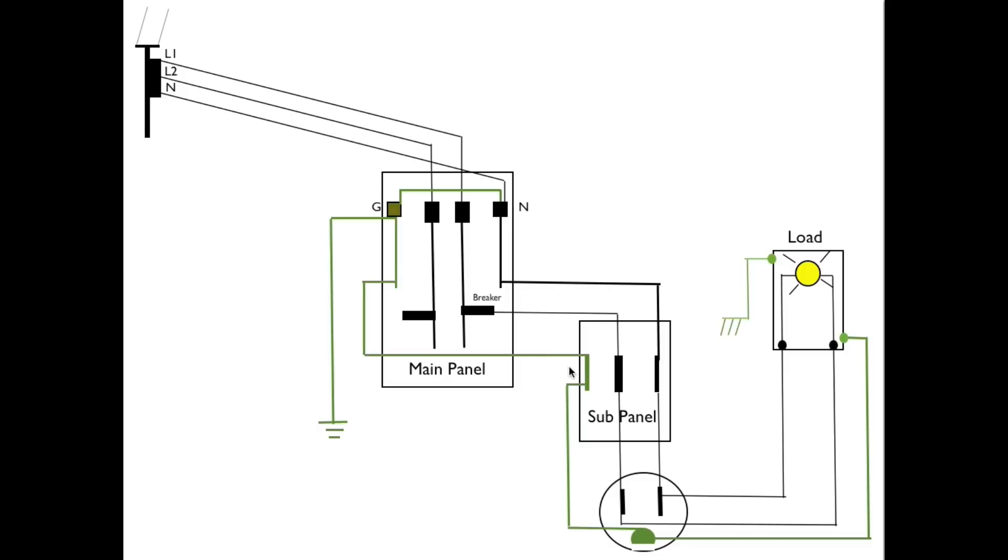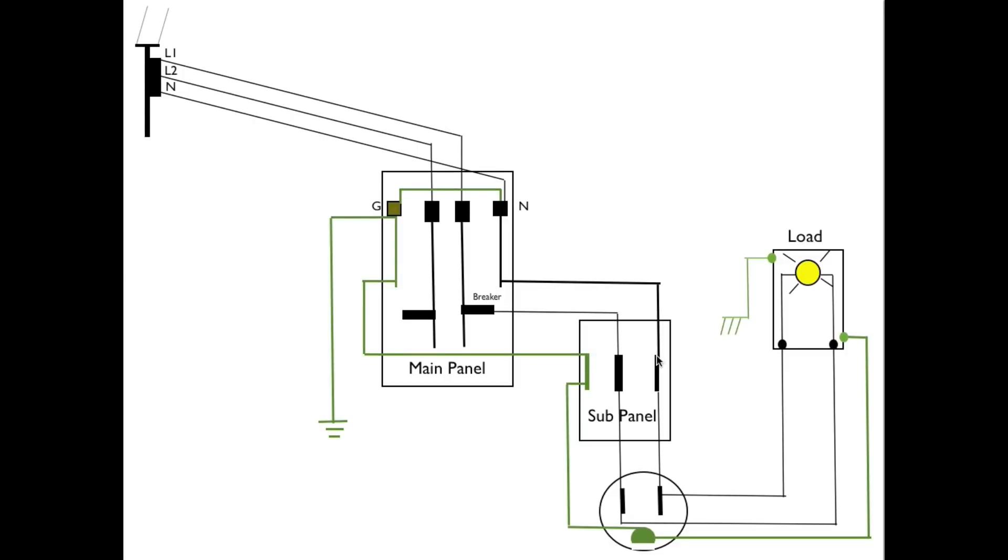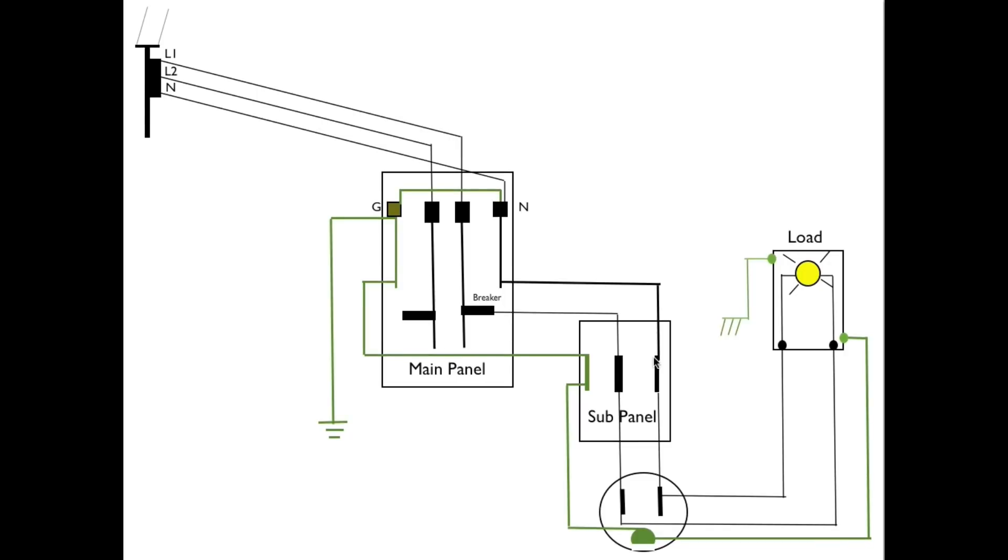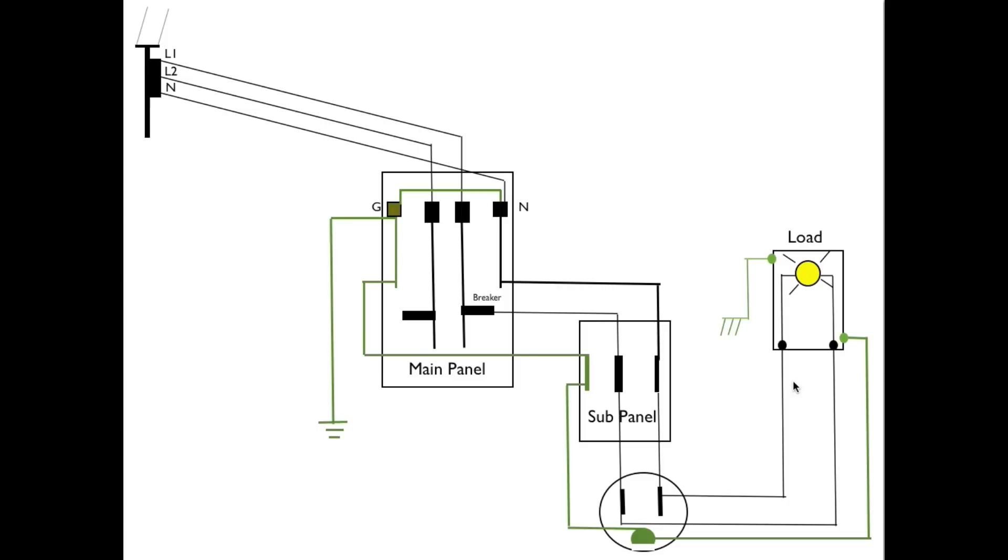If for some reason, if I had connected these two together right here, and then I had a fault where this wire failed, this neutral wire failed, then the load would run normally and it would go back through the ground. It would come through here, here, here, and then go back through the ground and back to the panel. And there would be no, the breaker wouldn't kick off or anything like that. However, you've just made this panel hot again. So you don't want to have those connected because you want the circuit protection to kick it off if one of these fails.